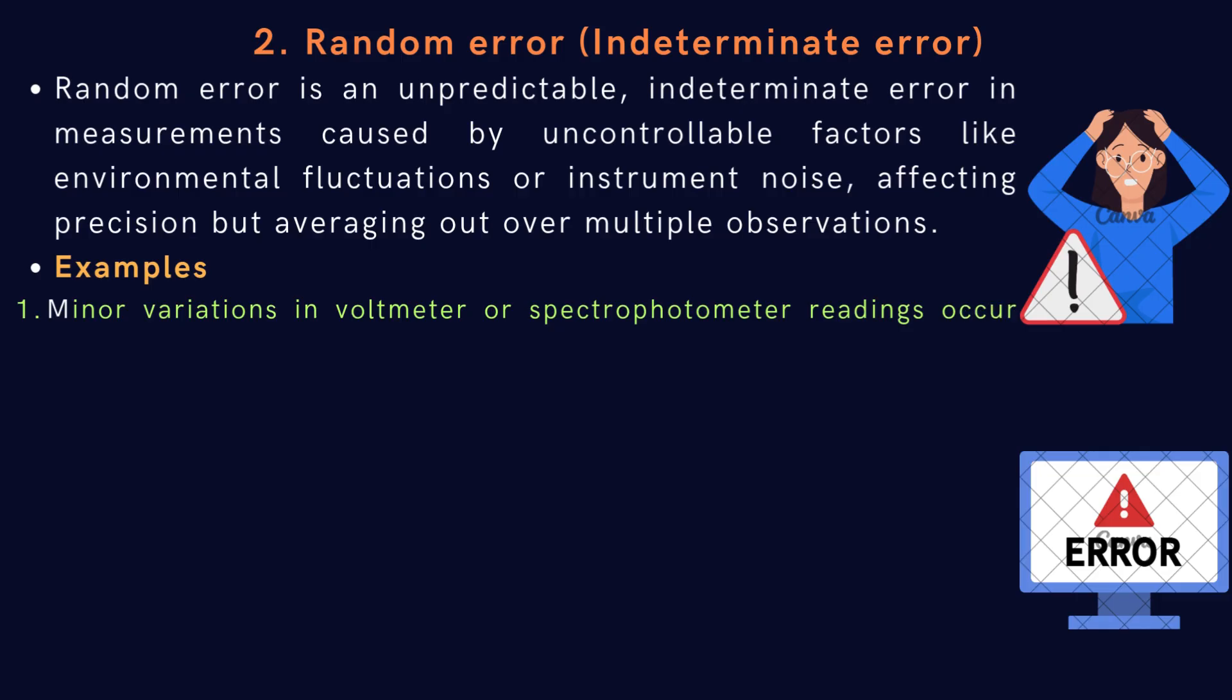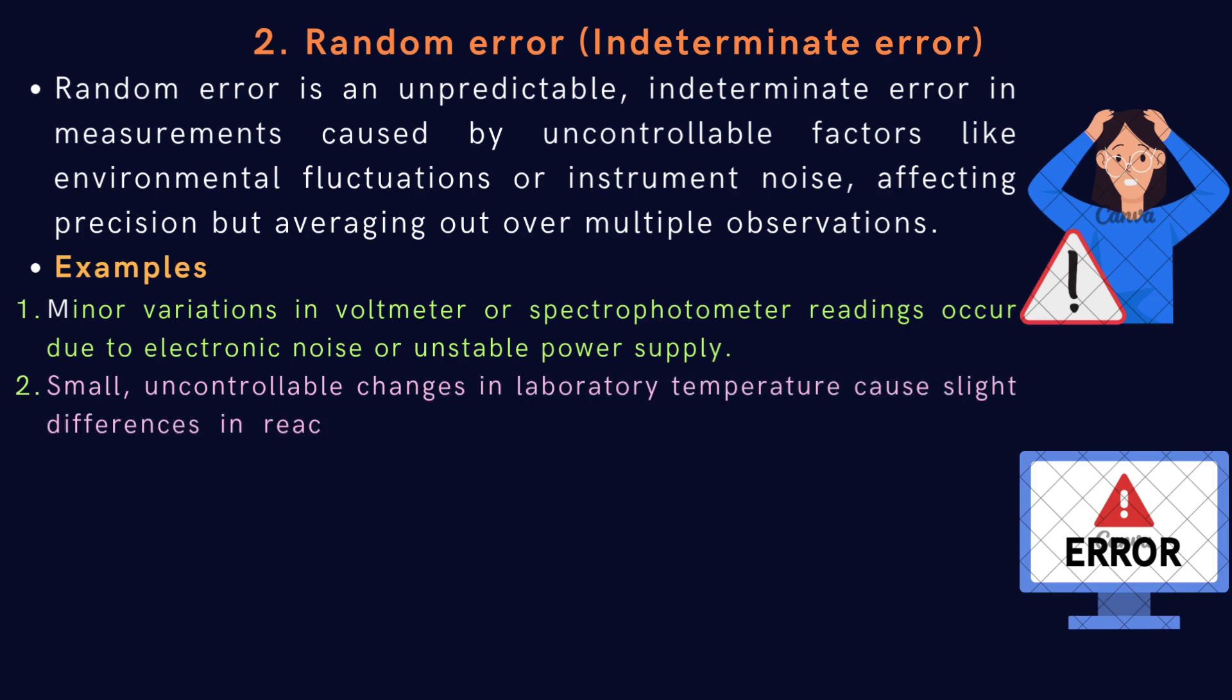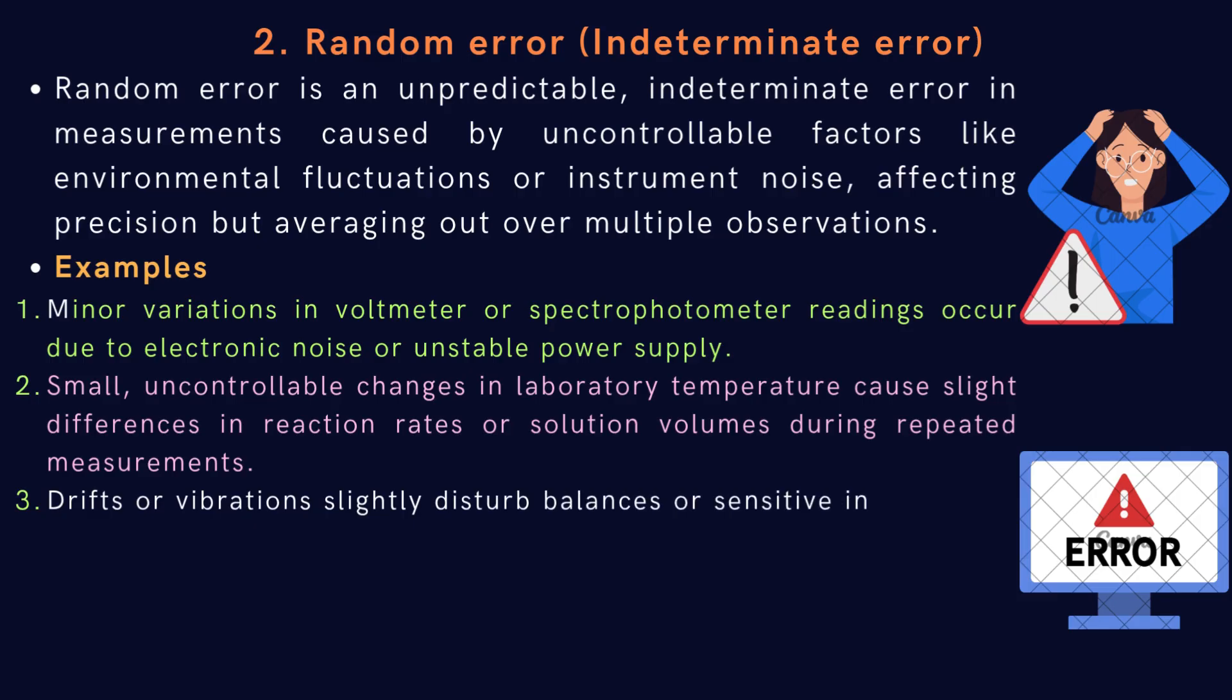Examples: minor variations in voltmeter or spectrophotometer readings occur due to electronic noise or unstable power supply. Small, uncontrollable changes in laboratory temperature cause slight differences in reaction rates or solution volumes during repeated measurements. Drifts or vibrations slightly disturb balances or sensitive instruments, causing small, irregular deviations in measured values.